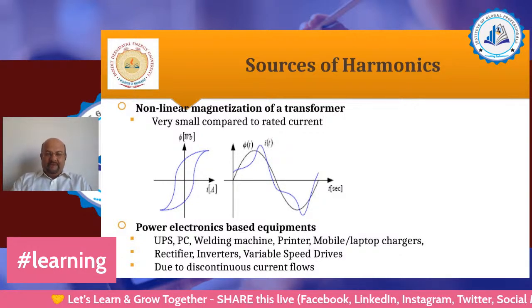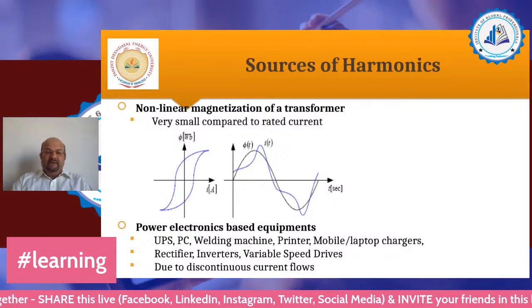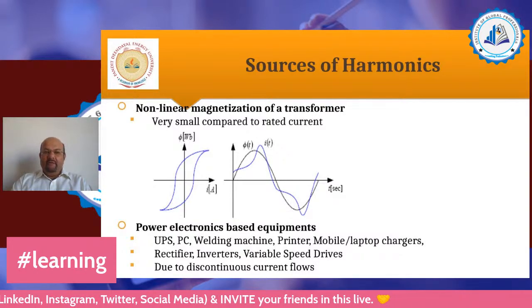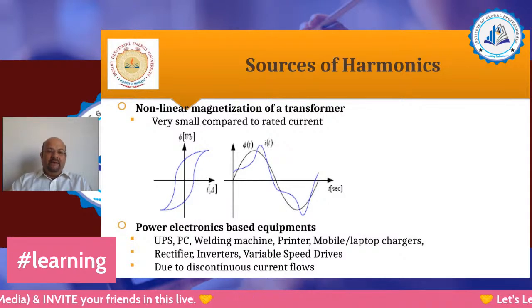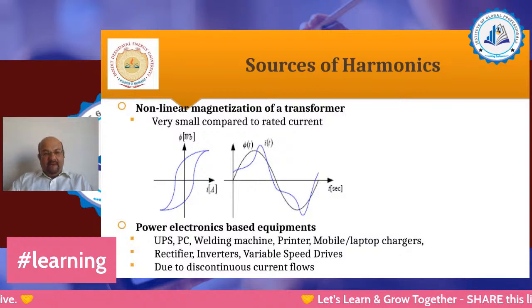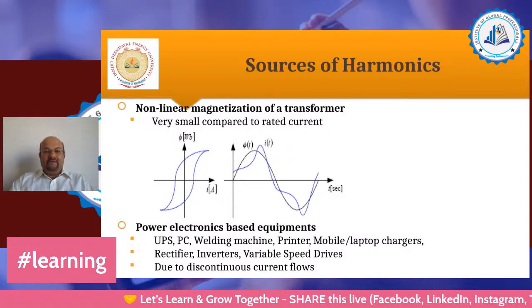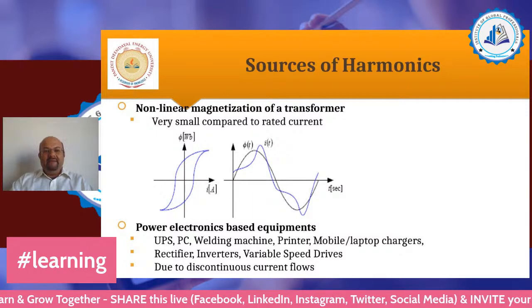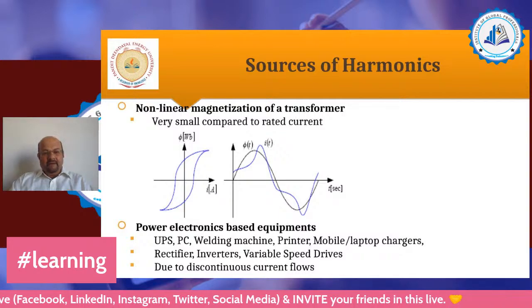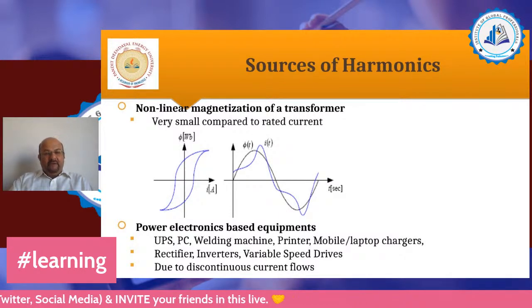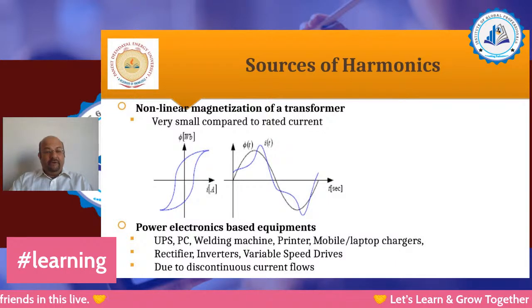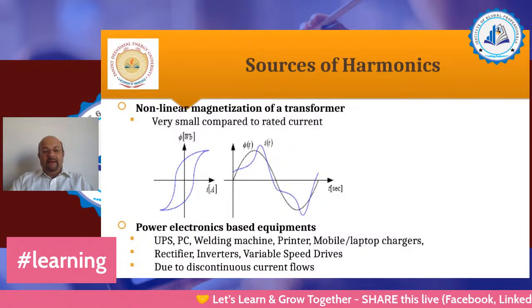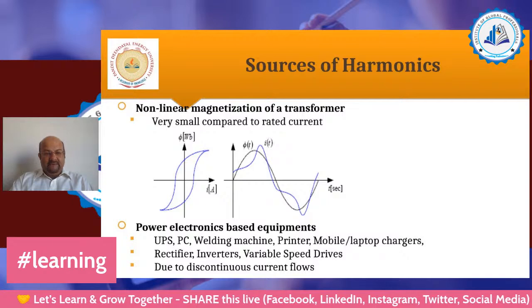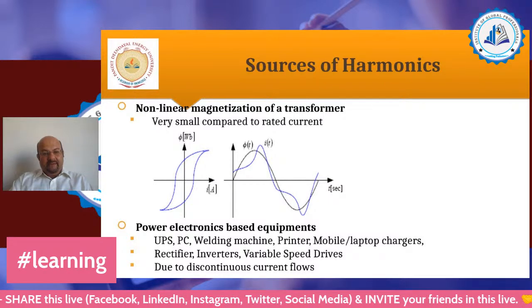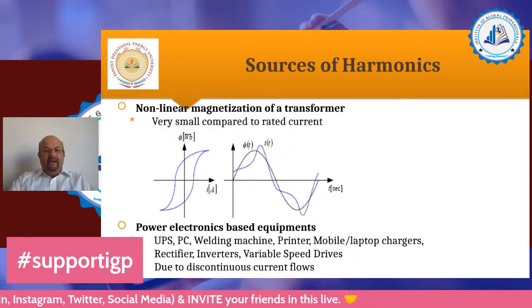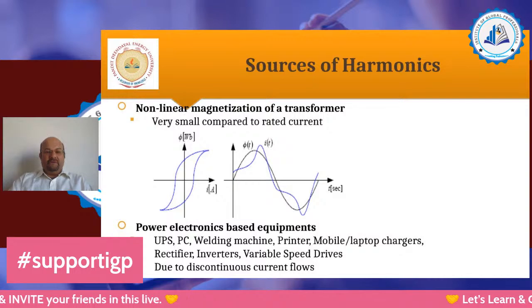Now let us talk about the source of harmonics. From where do harmonics generate? Any non-linearity in the transfer function of the equipment or the system will create harmonics. Here we can see that due to this hysteresis band, the voltage waveform has been deteriorated. Any such deterioration can be related to the introduction of higher frequencies to the fundamental one. Apart from this, power electronics based equipment like uninterrupted power supplies, personal computers where SMPS, switch mode power supplies, are used, welding machines, printers, mobile and laptop chargers, rectifiers, inverters, and variable frequency drives or variable speed drives, both are the same, due to discontinuous current flows. These are all sources of harmonics.